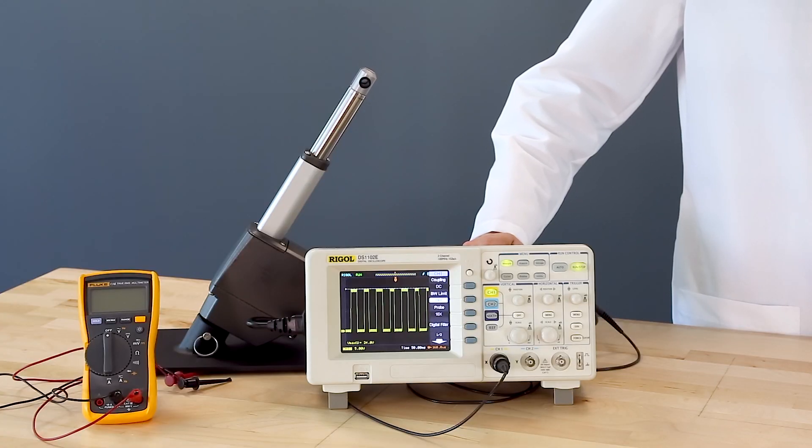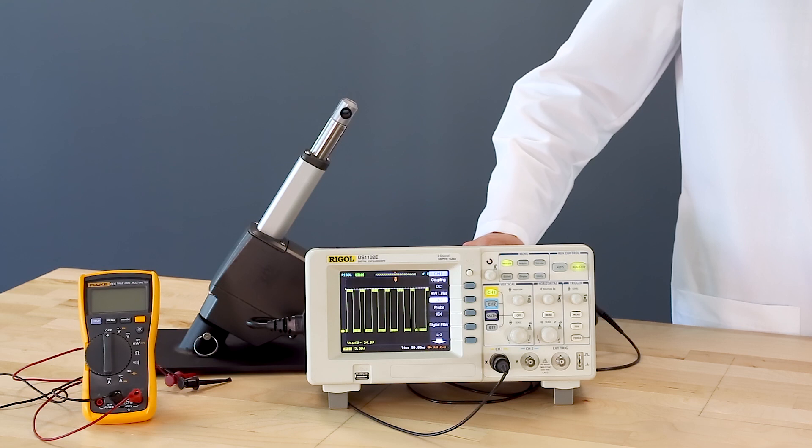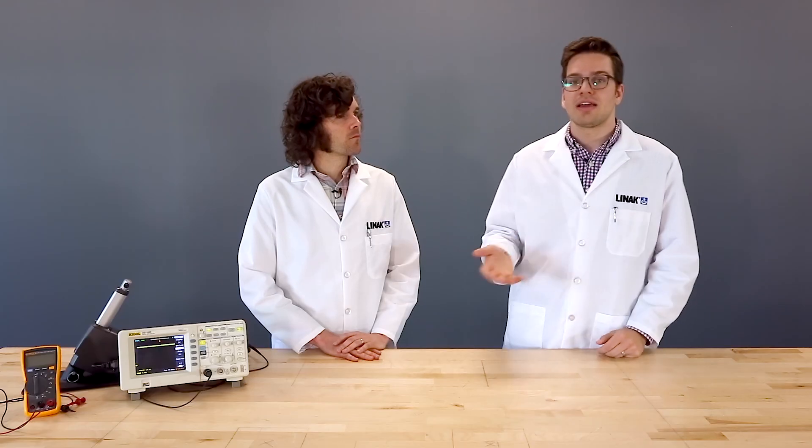So in a Hall effect sensor, the DC motor rotates the actuator spindle. As that spindle rotates, it rotates a set of magnets that the Hall effect sensor picks up the magnetic field change in. As it picks that up, the controller counts that, and that determines your position along the stroke.